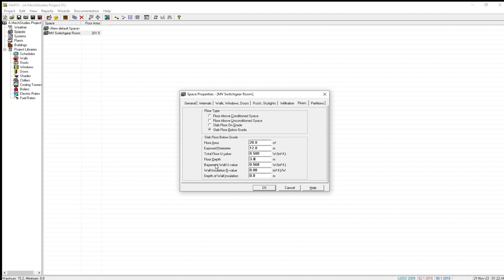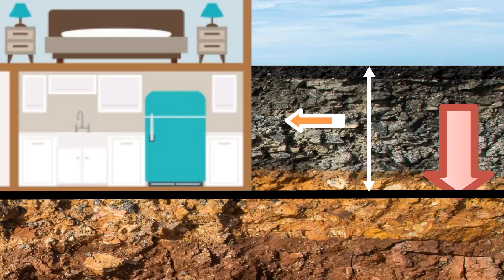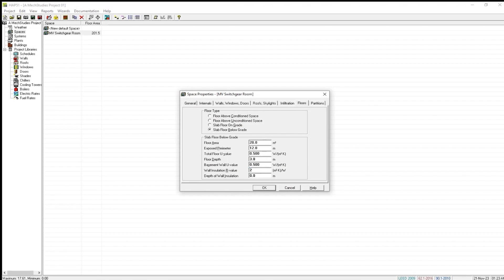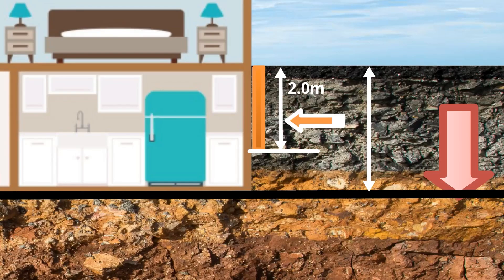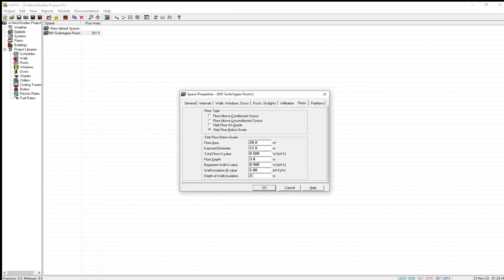The floor depth is 3 meters. The basement wall U-value default is 0.568, and we can keep it at 0.5 W/m²·K. The wall insulation R-value — we have given an insulation R-value of 2 m²·K/W — so we write 2. The depth of wall insulation considered in this building is 2 meters, so we put 2 meters. We have now completed the input for slab floor below grade, so let us click OK.